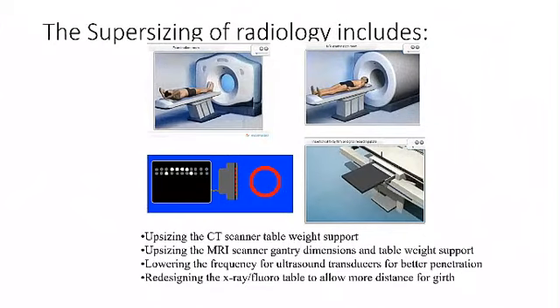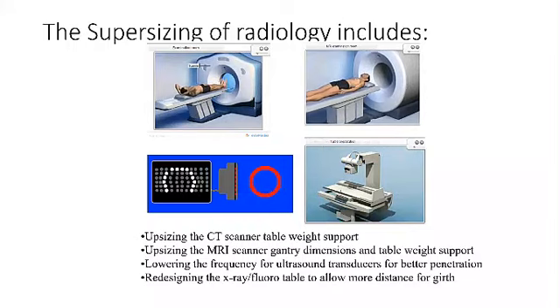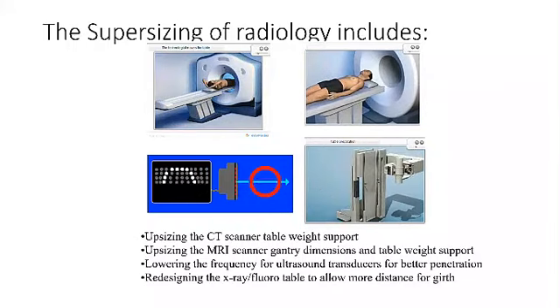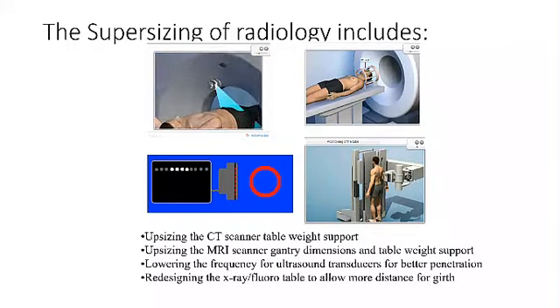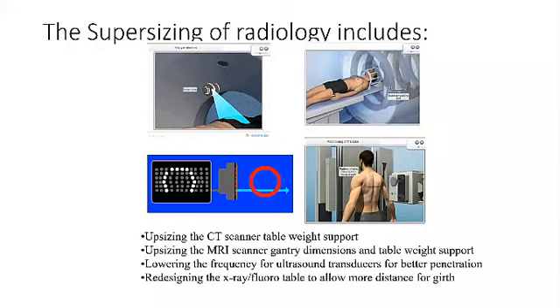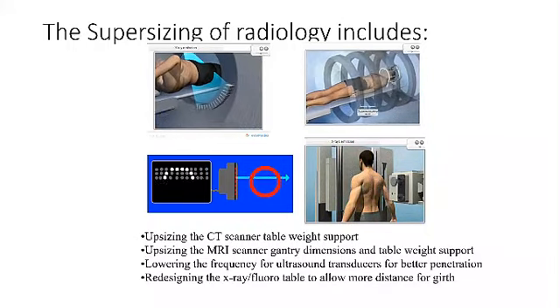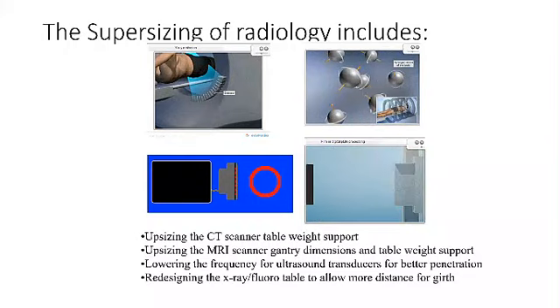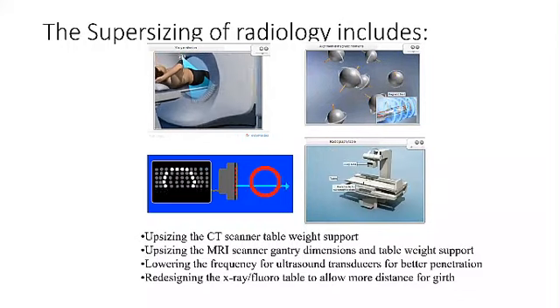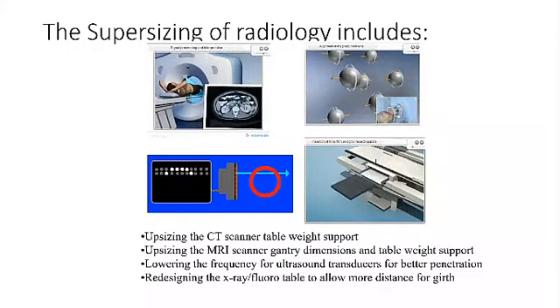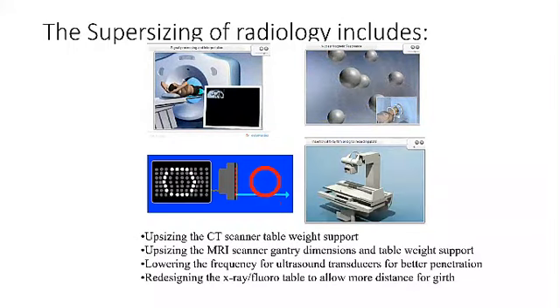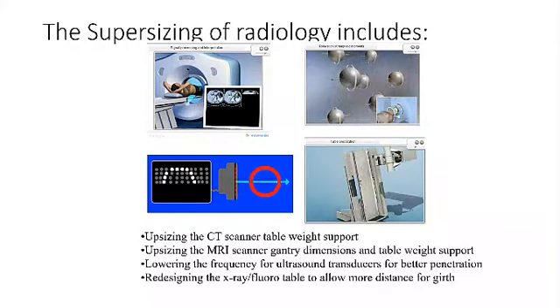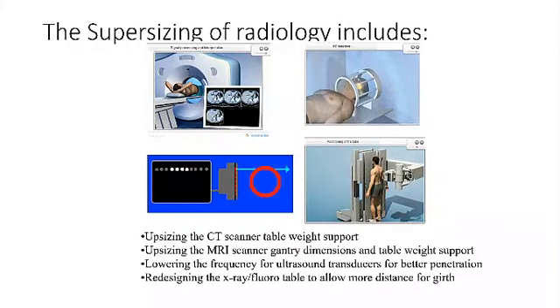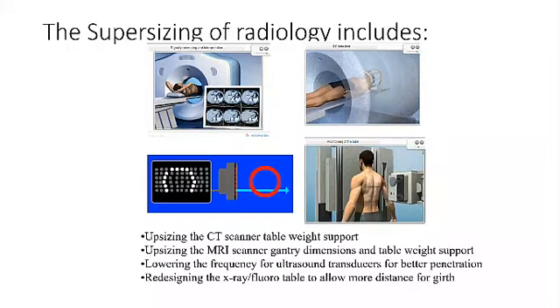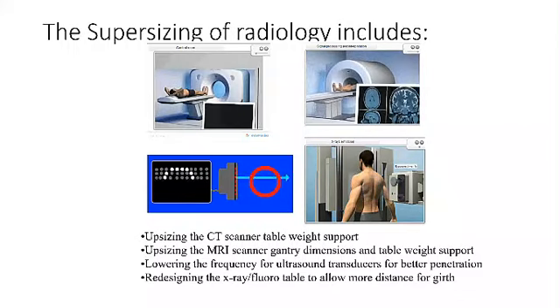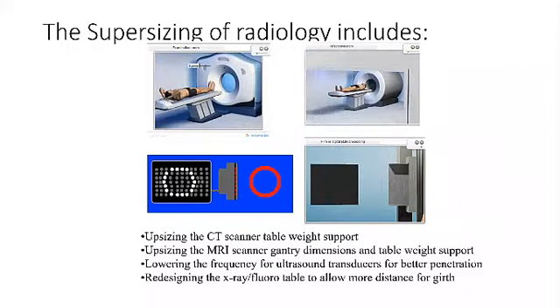So let's see what happens and how we supersize our radiology department. We'll look at plain radiography, CT, MRI, and ultrasound. Upsizing the CT scanner would mean that we'd have to increase the table weight support and maybe increase the aperture diameter for the patient to go through. The same with MRI, table support, and diameter of the MRI. We now have what's called wide bore MRIs. When we look at ultrasound or sonography, lowering the frequency for the ultrasound transducers will give us better penetration. And of course, for plain radiography, we need to upgrade the table weight support and redesign the X-ray and fluoro table to allow more distance for girth.